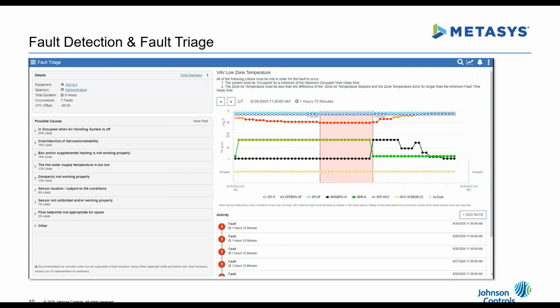Looking to the right top, I see the name of the fault, but also all the criteria with which this fault would occur. For this one, it needs to be occupied for a certain amount of time, and the zone temperature needs to be a distance away from the set point for a certain amount of time to go into fault. You'll also see a graph.